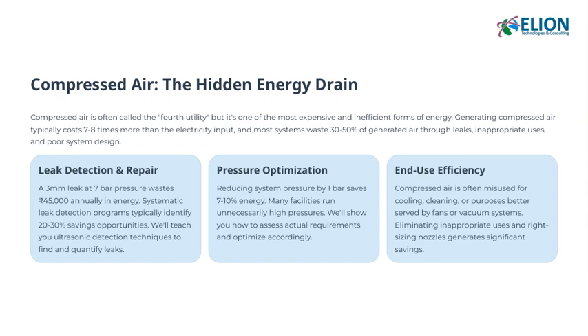This waste happens due to leaks, improper usage, and poor system design. Now, one of the biggest culprits is leaks. For example, a tiny 3mm leak at 7 bar pressure can waste around rupees 45,000 each year in energy costs. That's a huge amount for something so small. The good news is, through systematic leak detection programs, we can typically find 20 to 30% savings opportunities. We'll teach you ultrasonic detection techniques, which are highly effective for locating and quantifying leaks quickly and accurately.